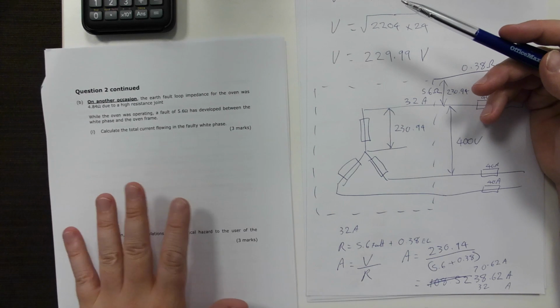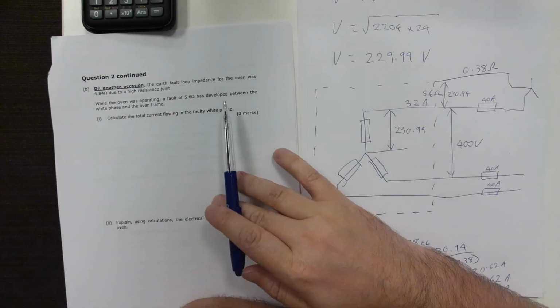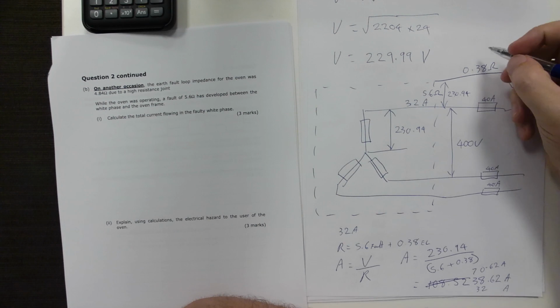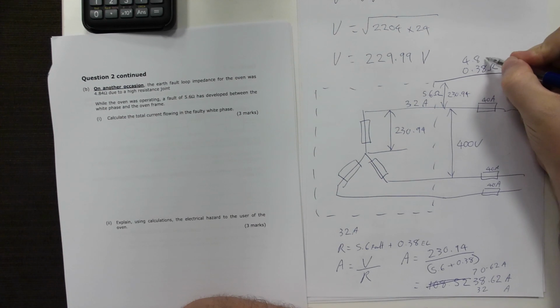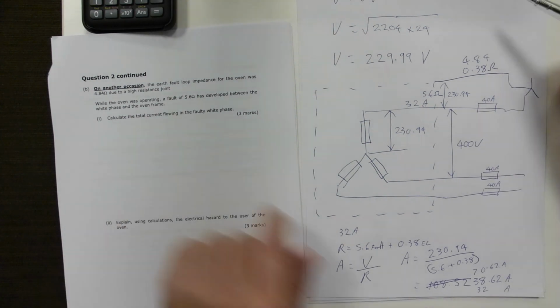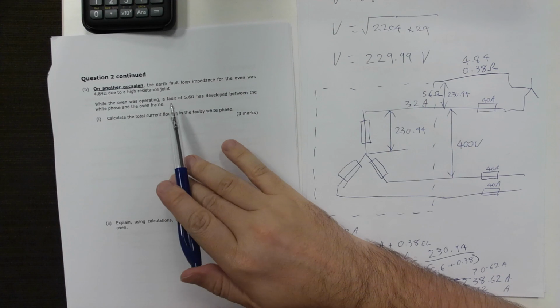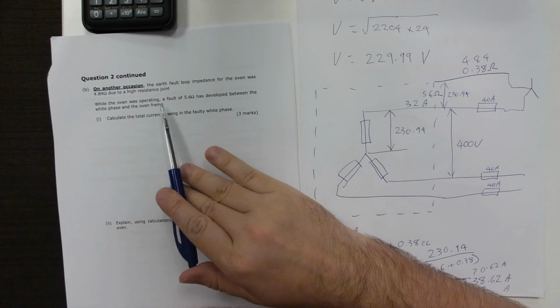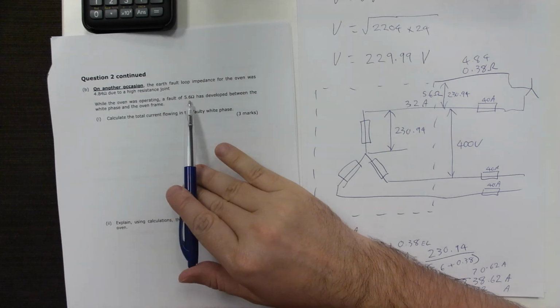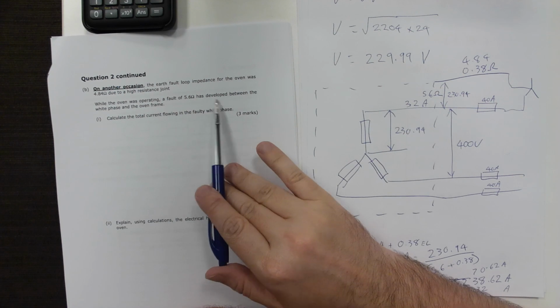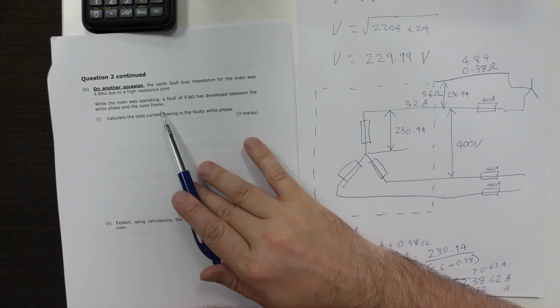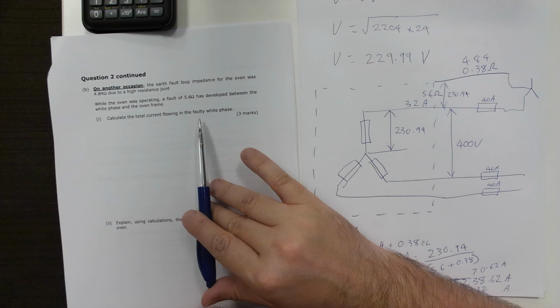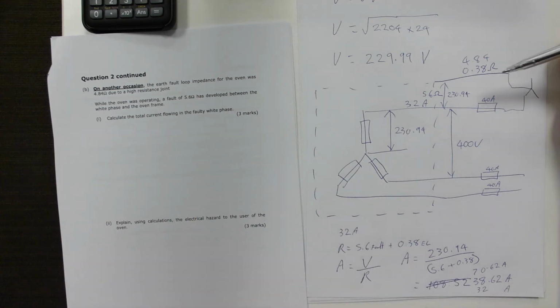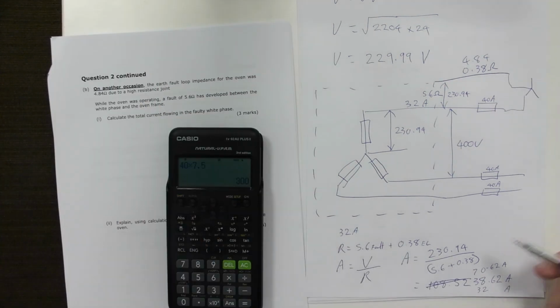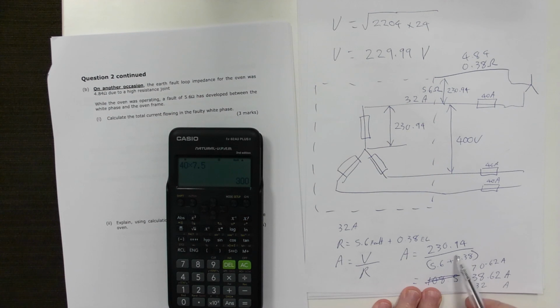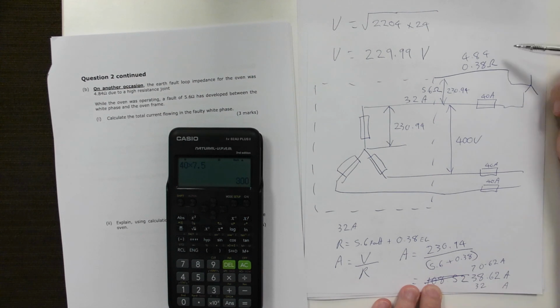On another occasion, the earth fault loop impedance for the oven was 4.84, so 4.8. Due to a high resistance joint while the oven was operating, a fault of 5.6 ohms developed, so it's still the same fault, between white phase and the oven frame. Calculate the total current flowing in the faulty white phase. So we're doing exactly the same equation. The only difference is instead of 0.38, we're using 4.84.